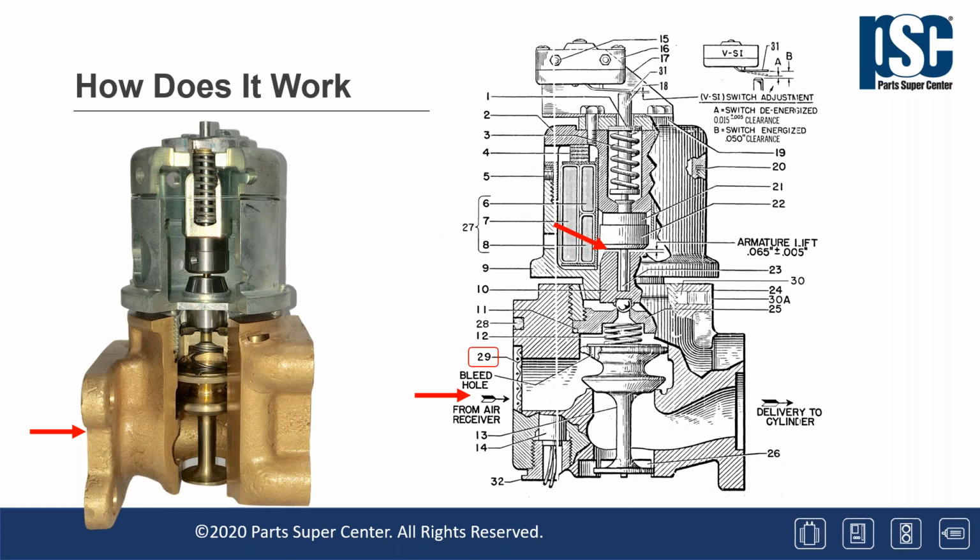Like just about any other electromechanical device, in order to be able to set up a control valve or even troubleshoot a control valve, you need to understand how it works. We're going to start by talking more about the complex control valve that's used on the majority of the mechanisms in service, which has 3 independent windings in the control valve coil. Let's start by assuming that the circuit breaker is in the open position and the air receiver is fully pressurized and that the circuit breaker is sitting idle awaiting a signal to close.